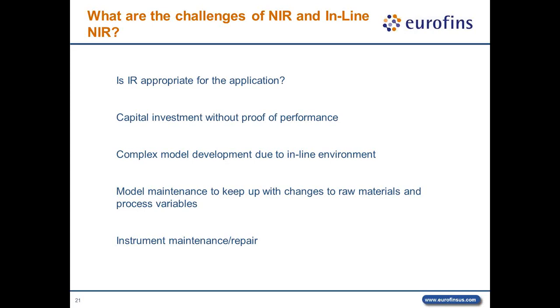Model development and maintenance is at the heart of the service we provide to our customers. The models are just as, if not more, important than the instrument and hardware used to collect the spectrum. Oftentimes, instrument manufacturers will provide initial starter models populated with a basic sample set. Oftentimes, this is good enough to get a system running, but rarely is it sufficient to provide accurate results over time. These models then require a significant amount of additional development in order to have robust models that you can rely on. QTA manages the entire process to ensure that whatever decision the customer makes, they were fully informed, had sufficient performance data to draw a conclusion, and had the opportunity to do so without an investment or capital purchase.